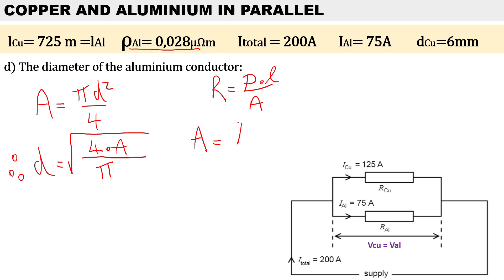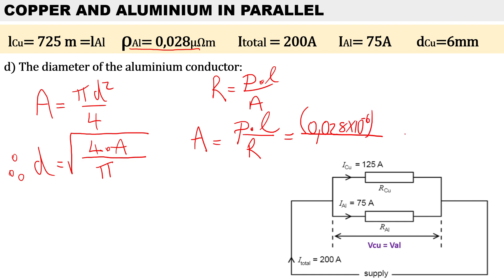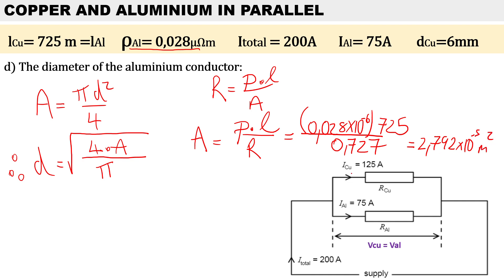To calculate the area, we manipulate the resistance equation: area equals resistivity for aluminium multiplied by the length of aluminium, divided by the resistance for aluminium. Don't forget to convert micro-ohm-meters to ohm-meters by multiplying by 10 to the power of minus 6. The cable length is 725 meters and the resistance is 0.727 ohms. Therefore the area is 2.792 times 10 to the minus 5 meters squared.